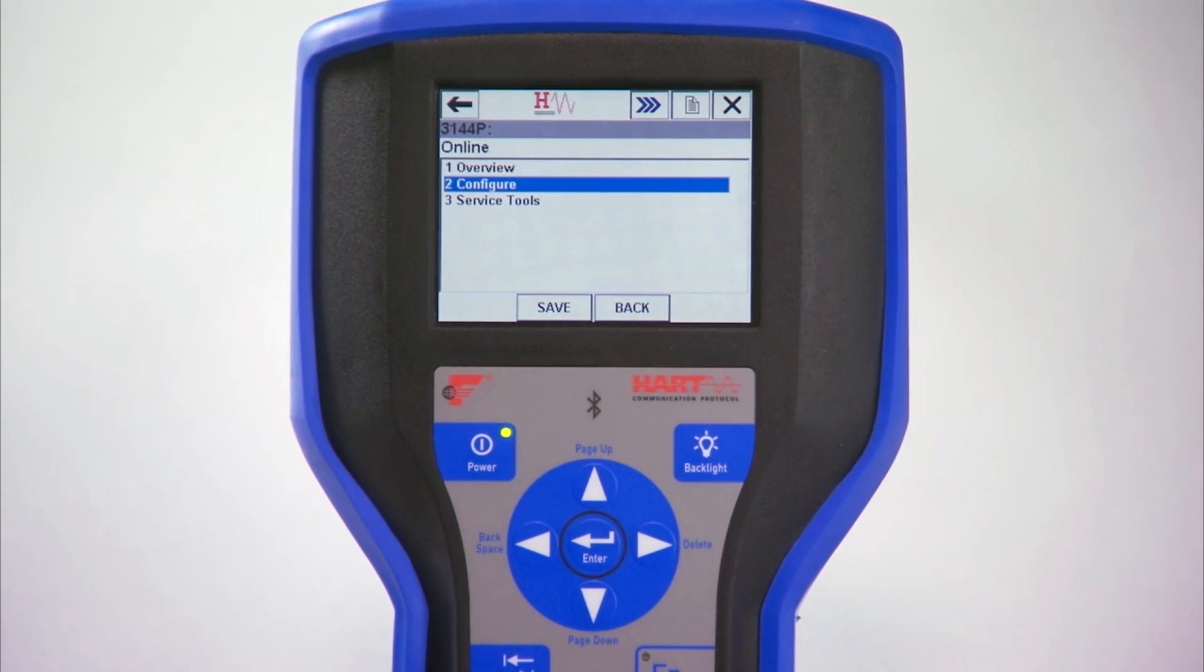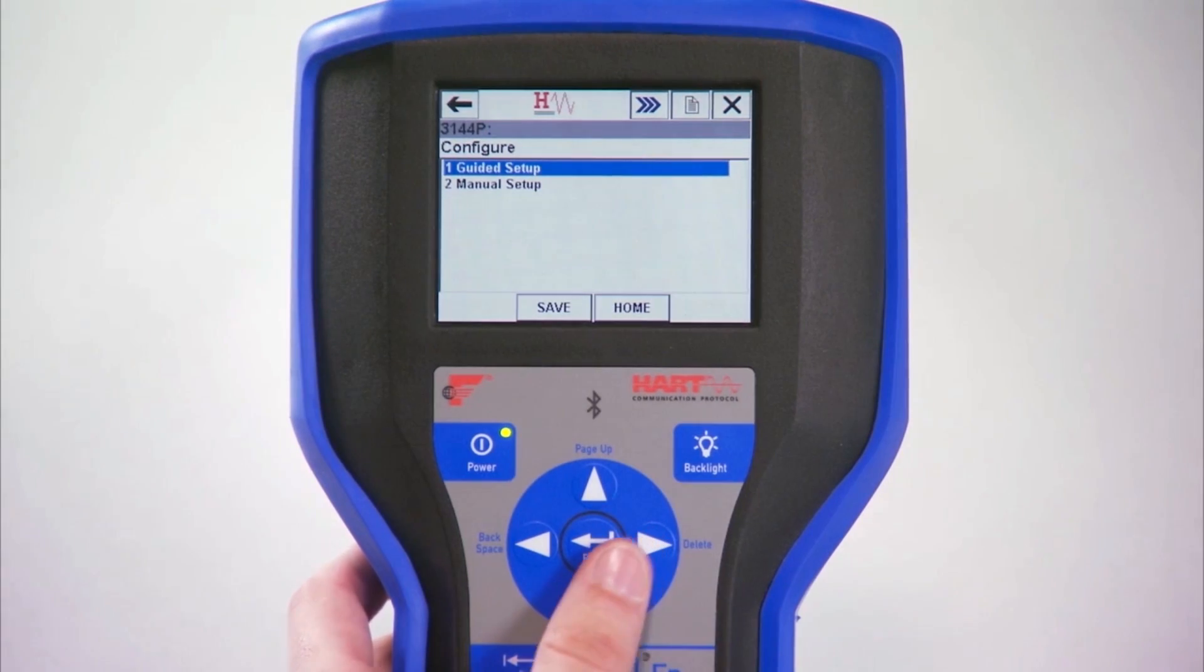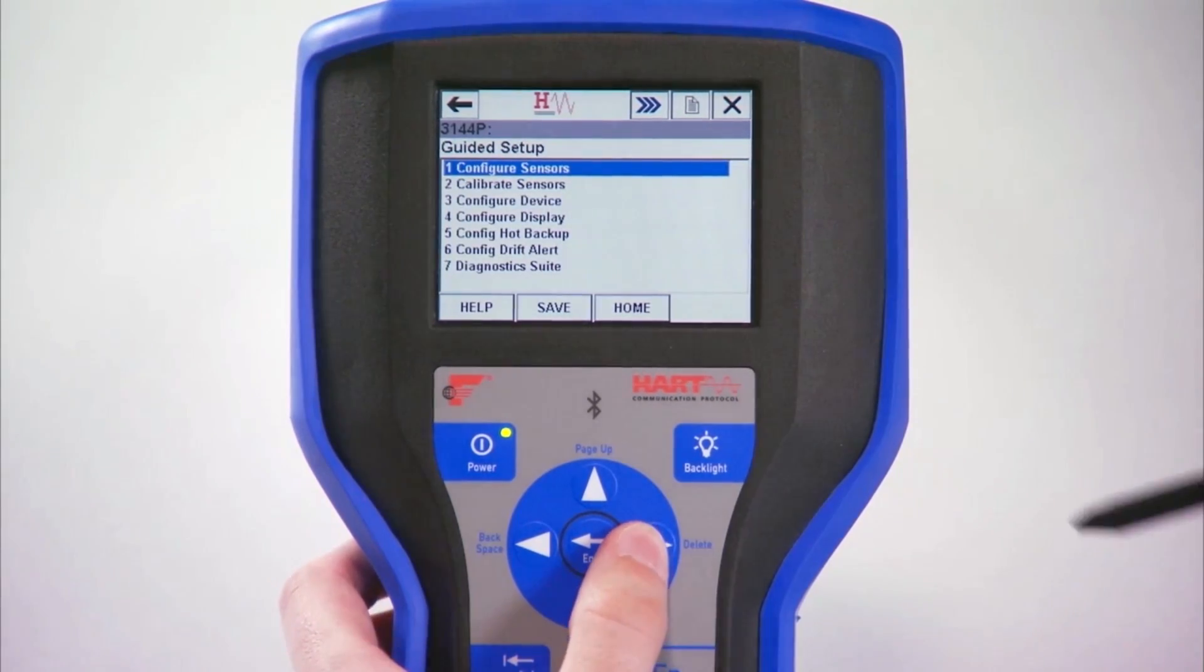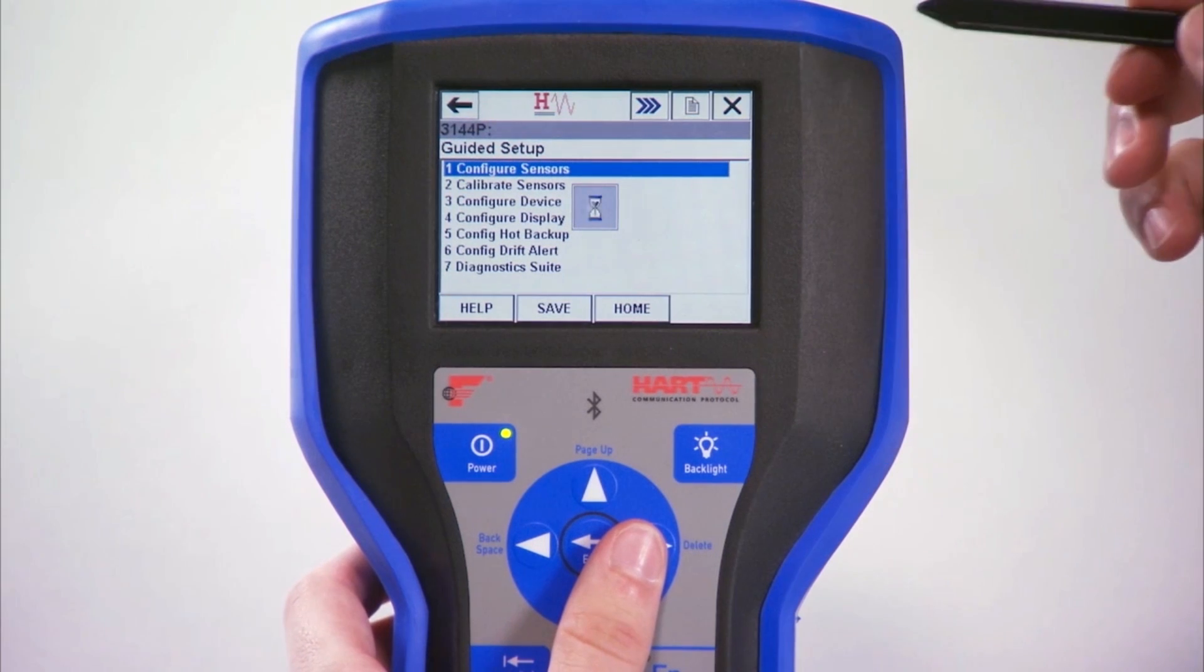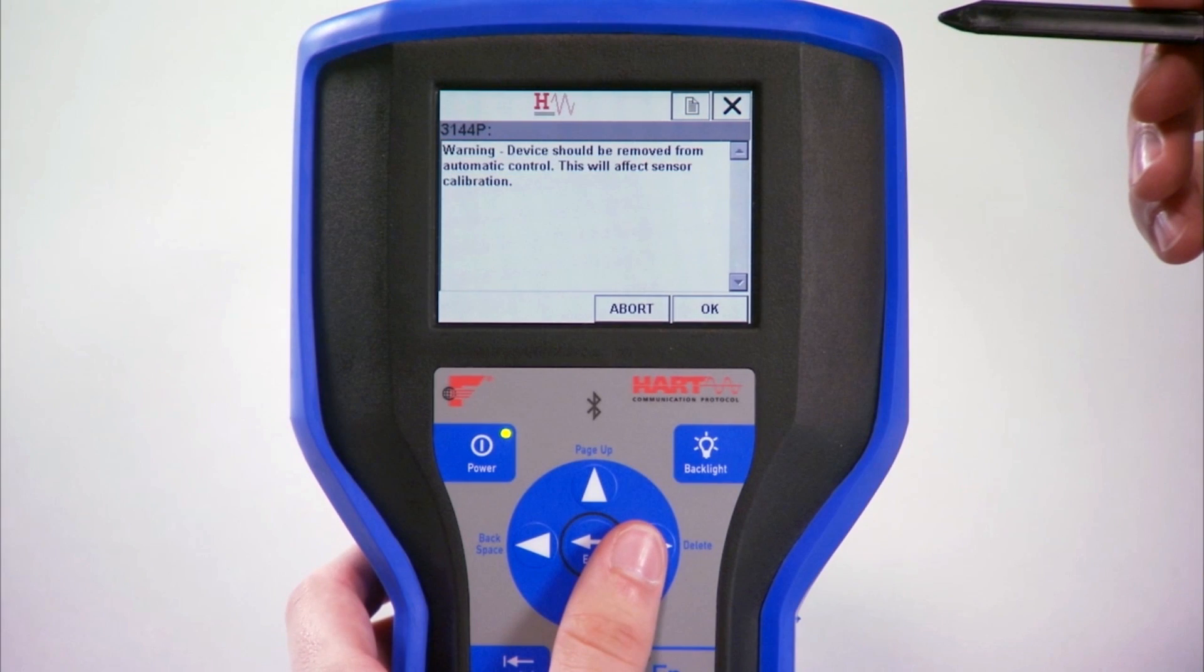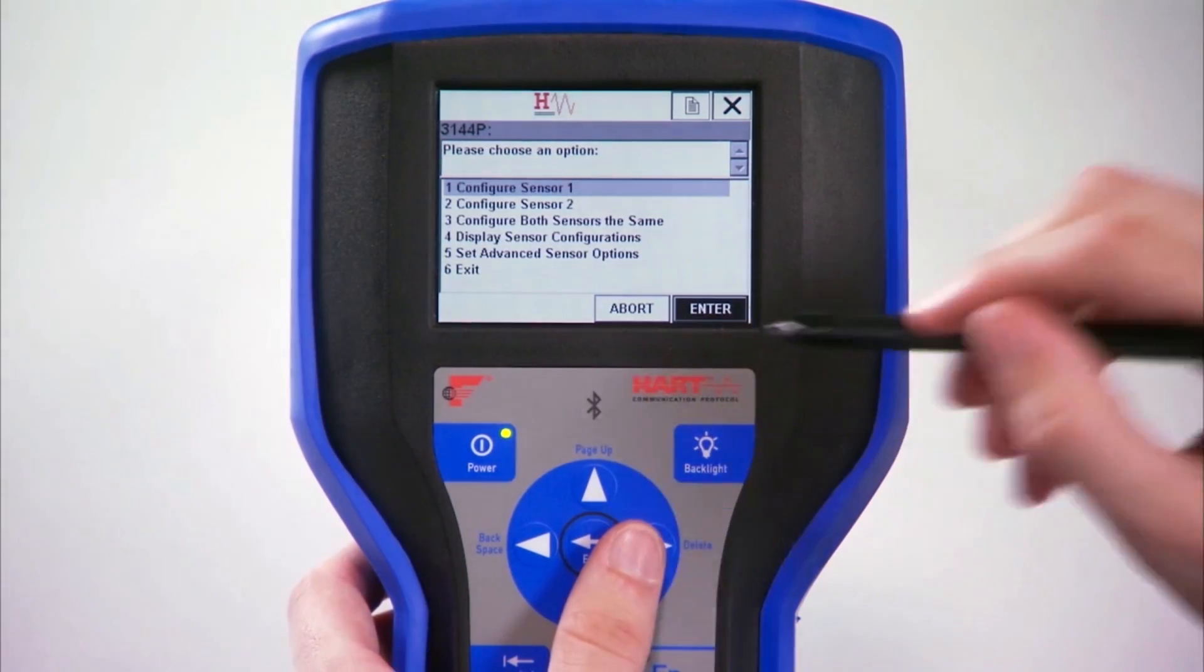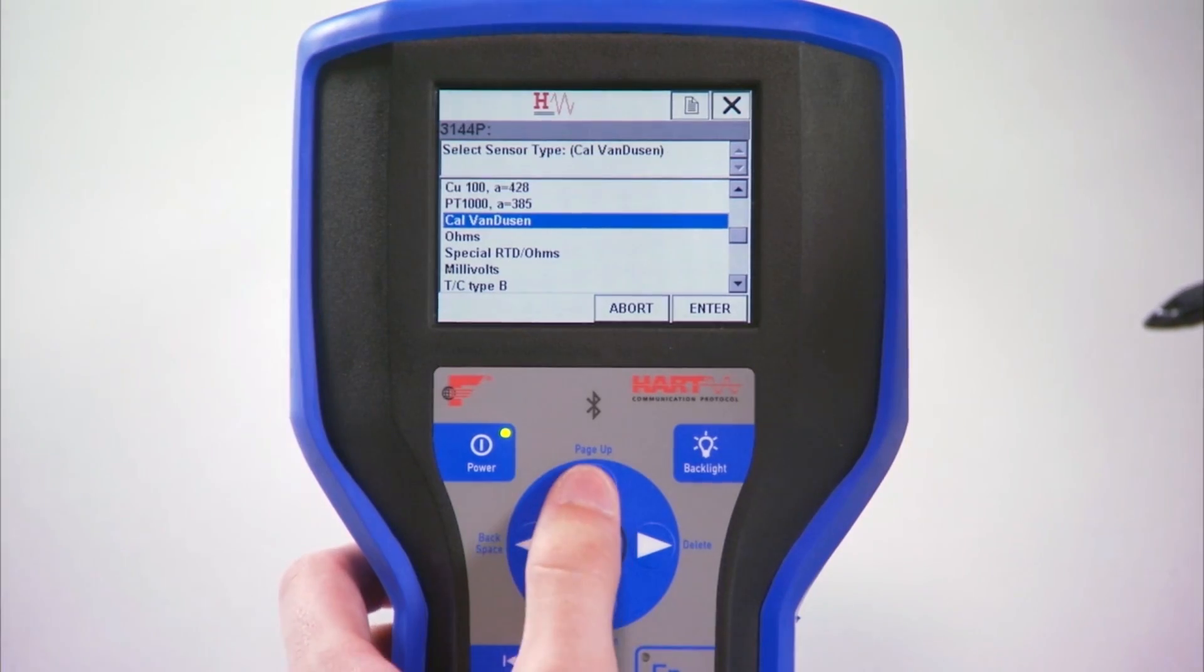From the home screen on a 475, click Configure, Guided Setup, and then Configure Sensor. A warning screen appears, explaining that the device must be removed from automatic control. Press OK. Then choose Configure Sensor 1 and press Enter.